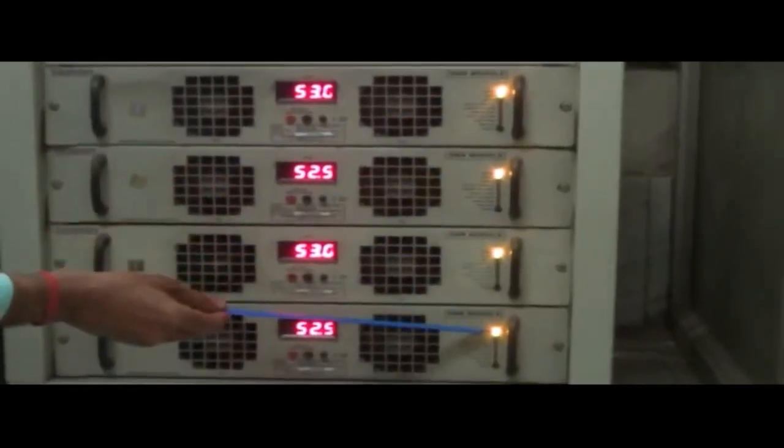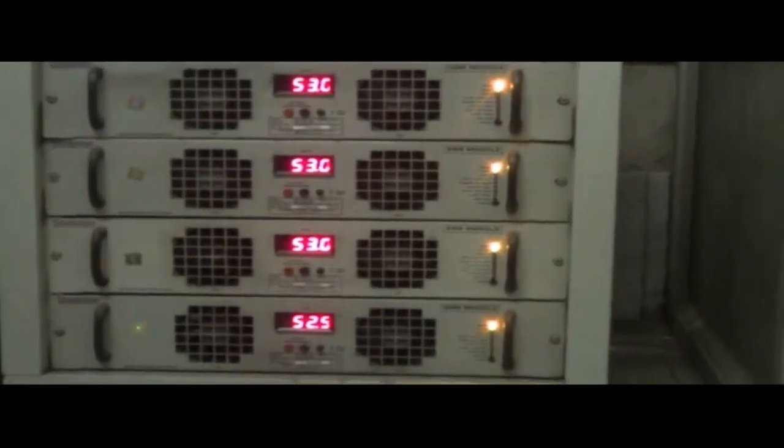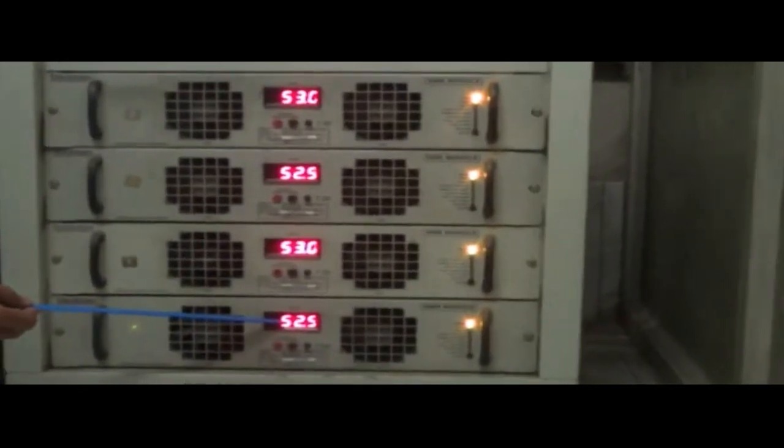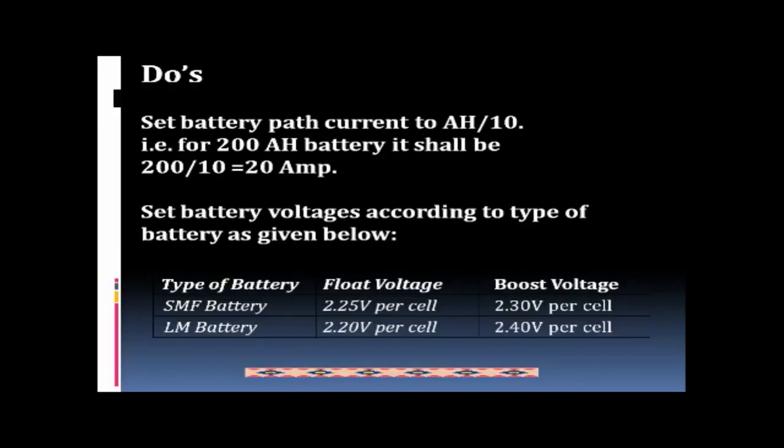Do's: Keep all the modules in on position. Set equal voltage in all modules for proper current sharing. Set battery path current to AH/10. Set battery voltages according to type of battery as given below. Type of battery: SMF battery, float voltage 2.25 volts per cell, boost voltage 2.30 volts per cell.